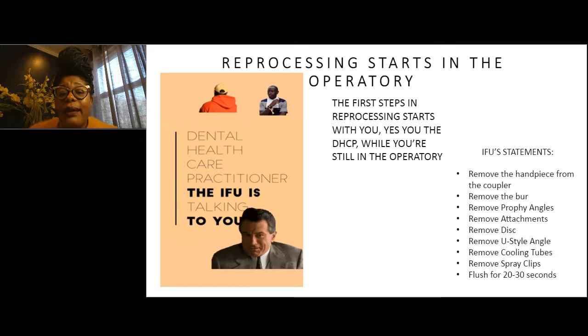Here, I place this to let you know that reprocessing really starts within the operatory. The reason why I say that is because many IFUs, and we're going to go into this, will have statements such as, remove the handpiece from the coupler. Where's the coupler found? It'll say, remove the burr. That's usually found in the operatory. Remove the prophy angle, remove the attachment, remove the disc, remove the U-style angle, remove the cooling tube, remove the spray clip, flush for 20 to 30 seconds. All of these statements are found in IFUs, which leads us to believe that the reprocessing step starts with you within the operatory.